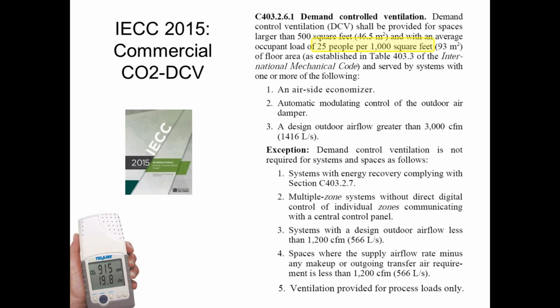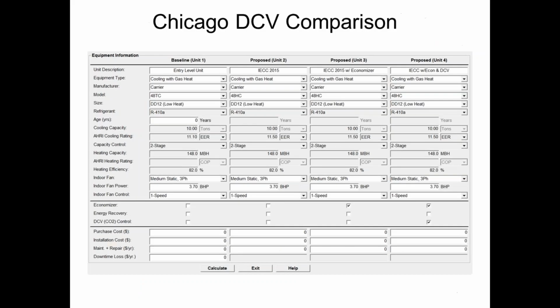So that's going to be movie theaters, conference rooms, auditoriums, stuff like that. Maybe an office with lots of cubicles that are relatively small. So pay attention to those, and you might have to put demand control ventilation in. There are some exceptions for systems that are fairly small or systems that already have ERVs anyway. But for most of your movie theater, auditorium, conference room, training room, classroom type spaces, you're probably going to have to do a CO2 sensor on your rooftop unit. So pay attention to that.